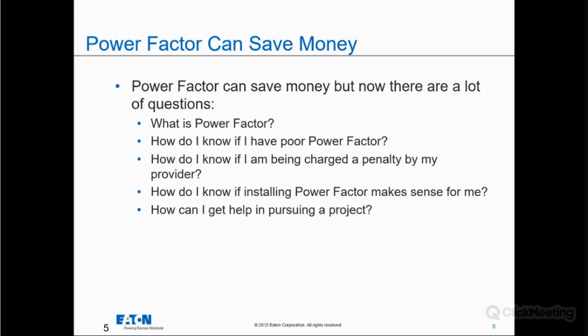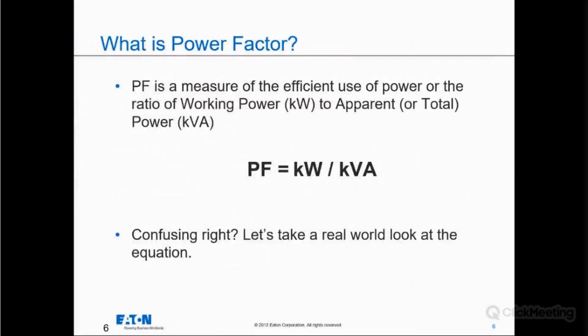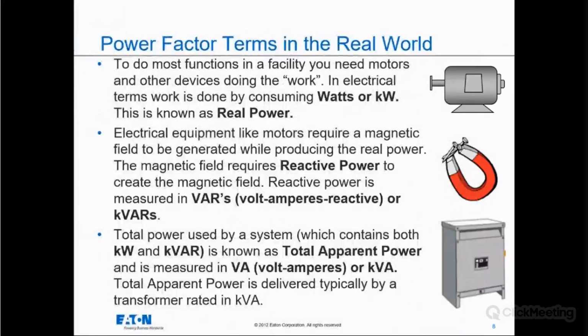So let's start off and get back to the basics. What is power factor? Power factor is a measure of the efficient use of power, or the ratio of working power, kW, to apparent power, kVA. Those terms look pretty familiar, kW, kVA, but maybe the whole concept of power factor is still a little confusing, right? So let's take a more simplistic, real-world look at it. If you own a factory, to do most functions in your facility, you need motors and other devices doing real, quote-unquote, work. In electrical terms, work is done by consuming watts, or kW, known as real power. Electrical equipment like motors require a magnetic field to be generated while producing the real power. The magnetic fields require reactive power to create that magnetic field.